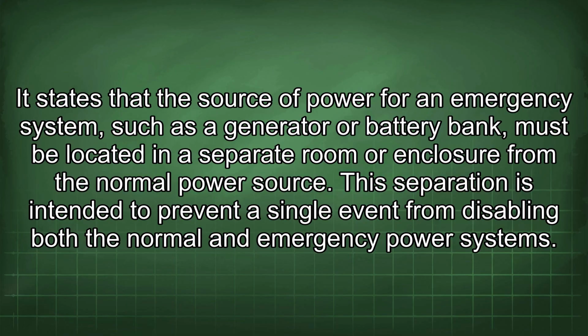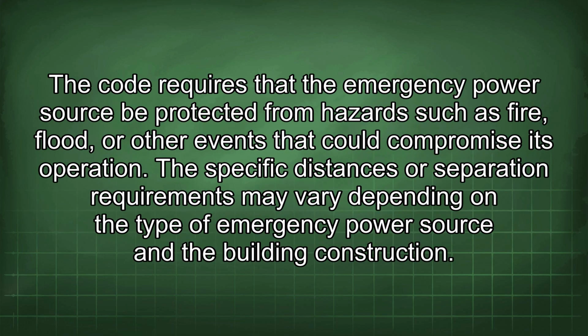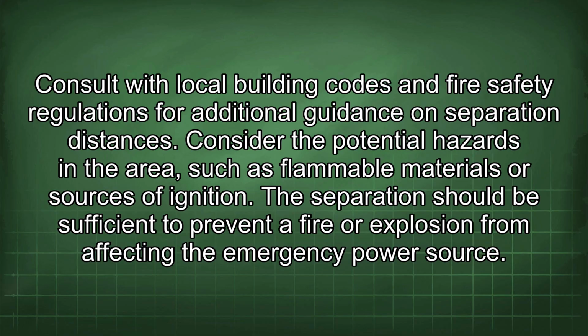This separation is intended to prevent a single event from disabling both the normal and emergency power systems. The code requires that the emergency power source be protected from hazards such as fire, flood, or other events that could compromise its operation. The specific distances or separation requirements may vary depending on the type of emergency power source and the building construction. Consult with local building codes and fire safety regulations for additional guidance on separation distances.